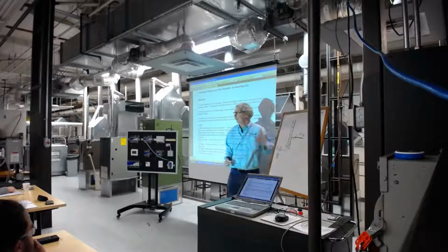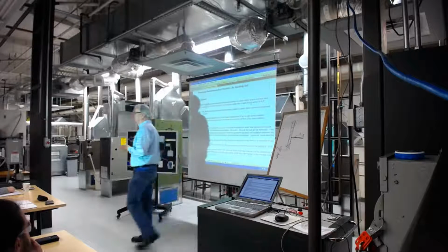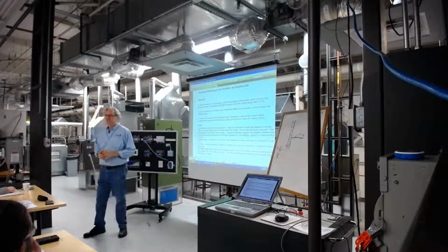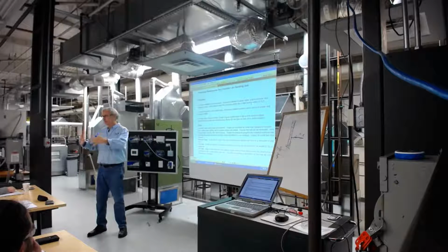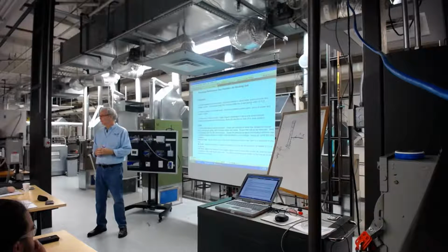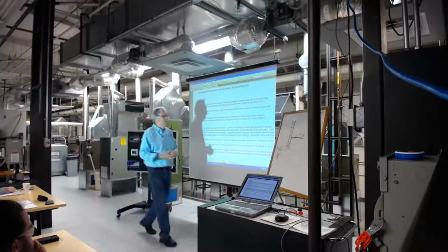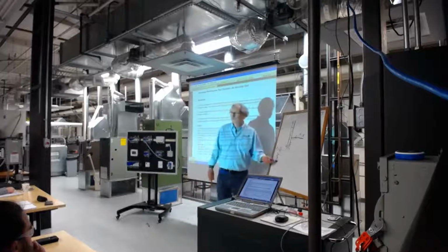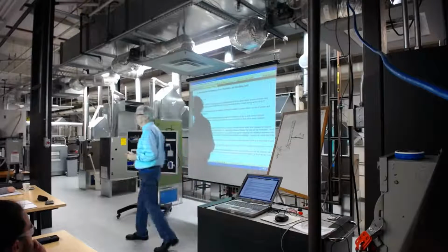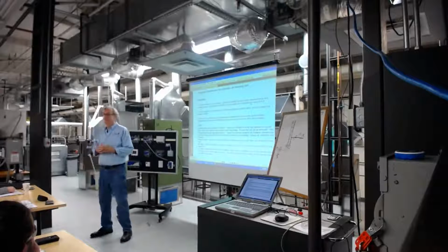We'll call the central plant, and we'll have them go into your water and drop it down. The chiller was designed at 45 degree discharge to get the most efficiency. We're going to drop the chilled water down to 43 degrees. Well, in some ways you'll make it worse, but more so, what did you just do? What happens when you drop that water down to 43?